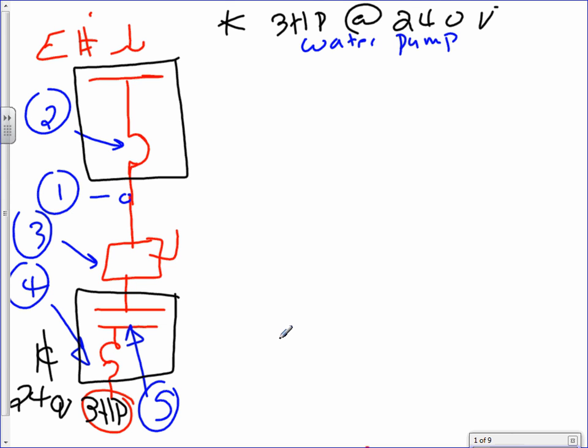All right. So one more time. This is my panel. Can you guys see this is my panel? Example number one, my panel. I took a branch circuit, overcurrent protection device, through a branch circuit conductor into a disconnect, into a controller, into an overload. Before we start, Matt, I want to review with you the function of each one of them. The main reason why we have a circuit breaker, number 2, is what? Short circuit and ground fault protection. The main reason why we have number 1, which is the branch circuit, is these are the interstate highways that transfer the electrical power into the pump so it can work.